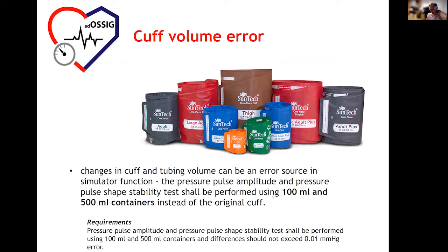And we envisaged some requirements, like how the pressure pulses should be tested, the amplitude and shapes to be tested using these two containers, and the differences should not exceed 0.01 mmHg error. So we did a lot of testing. We decided on a number. Now currently we are also testing commercial simulators, so as not to recommend too strict requirements for the simulators.